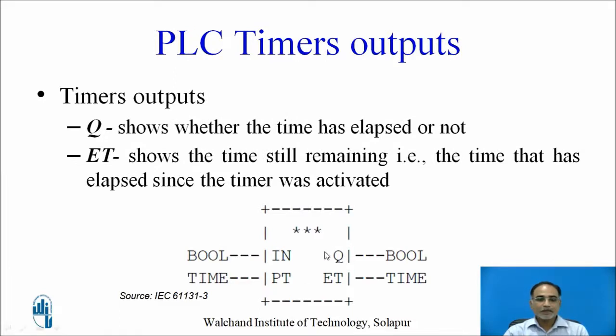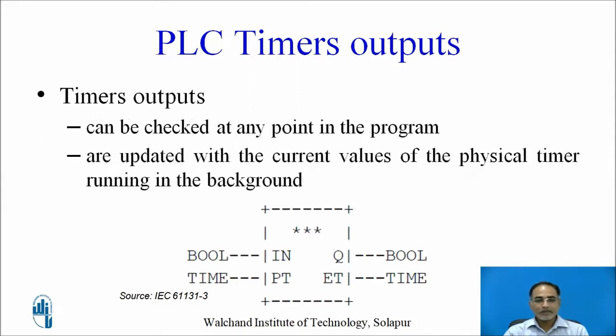There are two outputs on the timer. Q shows whether the time has elapsed or not; its data type is boolean, meaning you get either 0 or 1. The second output is ET, which stands for elapsed time — it shows the time that has elapsed since the timer was activated. Timer outputs can be checked at any point in the program and are always updated with the current values of the physical timer running in the background.